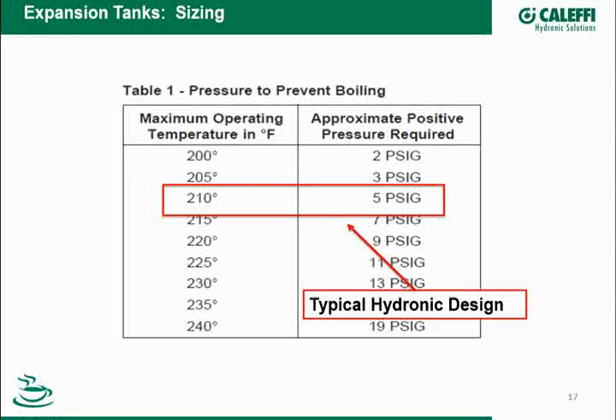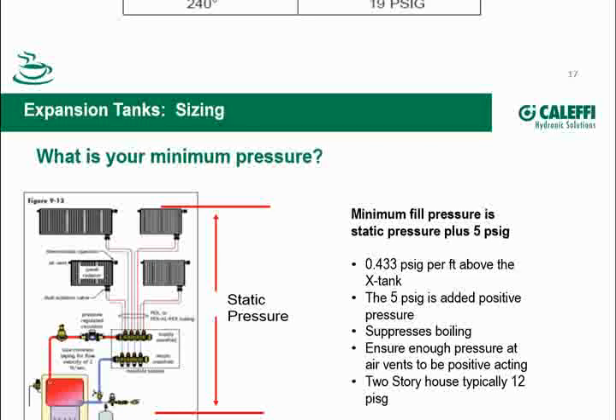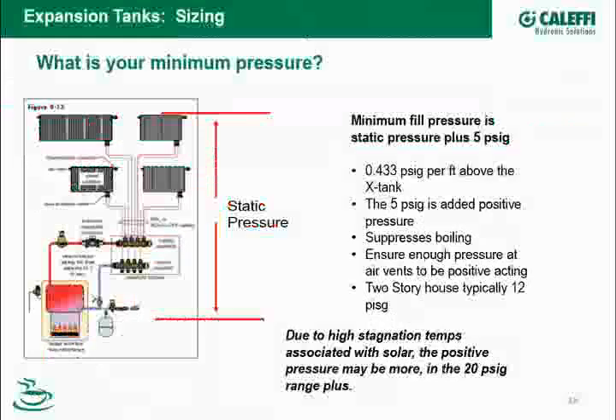So, what is my minimum pressure? First, I'm going to go with my 5 psi positive pressure at the top of the system. Then I have to figure out the static pressure of the system. I measure from the location of the expansion tank and the fill valve how many feet the top of my hydronic system is above there. Then I take that number of feet and multiply it by 0.433, and that will calculate the static pressure of the system. I then add that 5 pounds of positive pressure to it, and that will be the pre-charge on my expansion tank and the fill pressure on my fill valve.